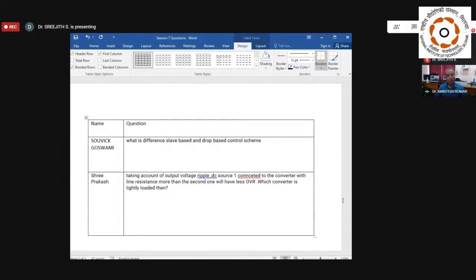In the normal power system, the grid is assumed to be the master. Master means who will be controlling the DC link voltage. That is the major issue. If you have the grid as master, then we assume the grid voltage is fixed at 230 volt or 415 volt. And whenever we integrate our distributed generation into the grid, we assume the DC is a slave. Slave means first the DC has to synchronize with the AC grid.